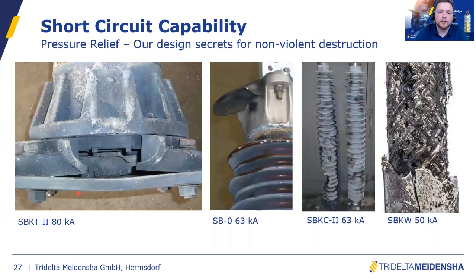That's why we include a kind of pressure relief device in hollow core surge arresters. On the left side, SBKT. It's a very nice example, an 80 kA short circuit test. You see this wide opening, and you also see that internally there's something defective, and this is a membrane that provides tightness to the surge arrester, but under short circuit condition, it will open and it will release all the pressure, all the hot air to the outside, and then it has a certain shape.